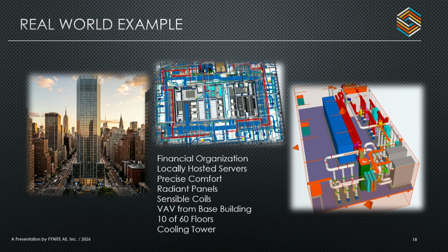So I'm going to give you a real world example. There's a financial institution here in New York City. It's a 60-story high-rise tower. They got the top 10 stories of that tower. They have locally hosted servers for trading. They wanted to provide their employees a precise indoor environment, plus or minus a half a degree. So to that goal, they gave them radiant panels in every room, sensible heating, sensible cooling coils on the trading floors, so in case anything went down, we could still cool. And we get a base building VAV system from DX air handlers that are attached to a cooling tower. And there's an image of the chiller room to the far right there, which shows we have redundant pumps and everything, so it's built like a data center on one floor.